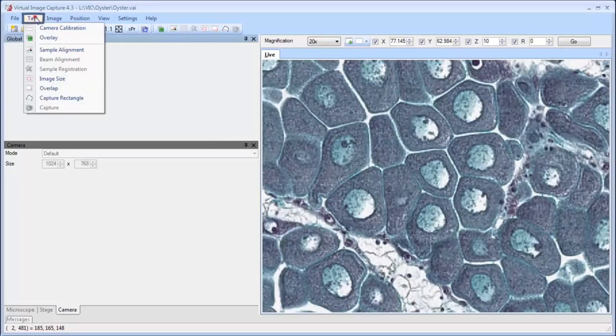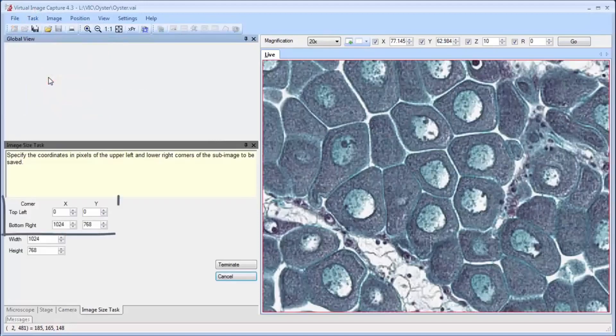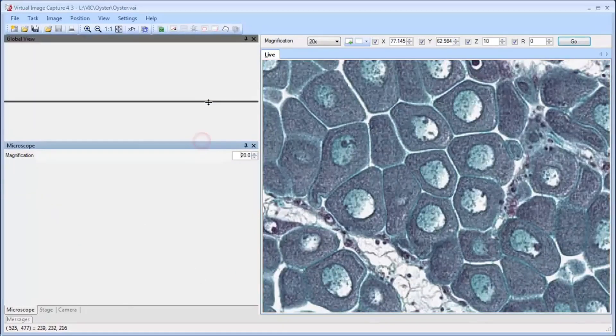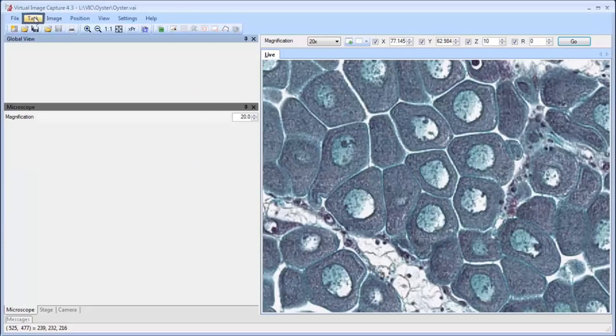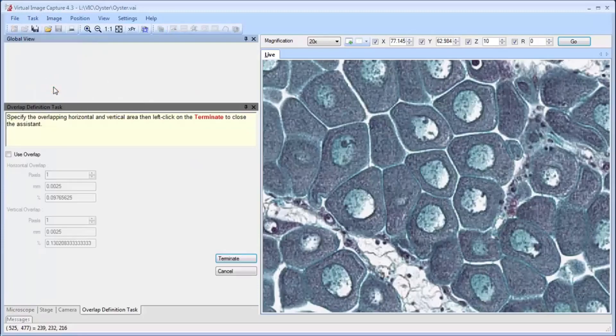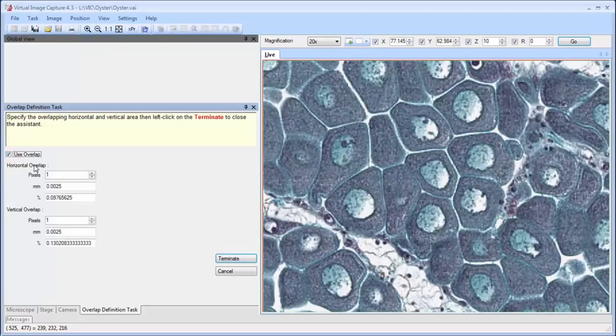Select the task, then image size, to define the size of the sub-image within the captured image. To define the overlap between adjacent fields, select task and then overlap. This helps to accurately stitch captured fields into one single large image, and is a fundamental concept for virtual slides and high-throughput imaging.